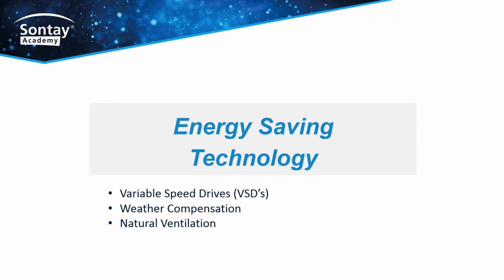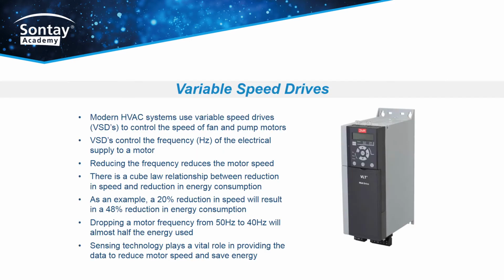Energy saving technology. We will cover variable speed drives, weather compensation, and natural ventilation. Variable speed drives. Modern HVAC systems use variable speed drives, VSDs, to control the speed of fan and pump motors. VSDs control the frequency in hertz of the electrical supply to a motor. Reducing the frequency reduces the motor speed.